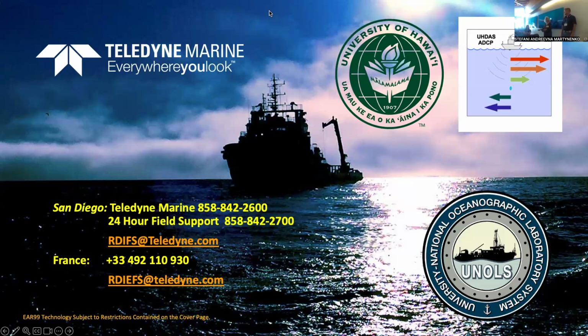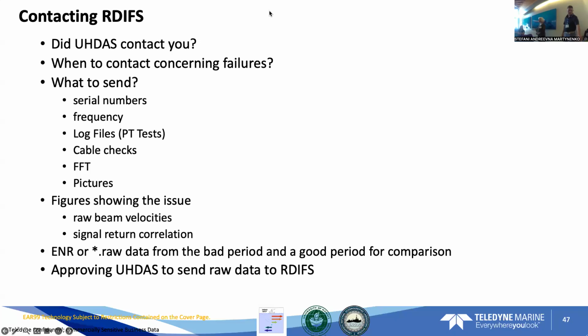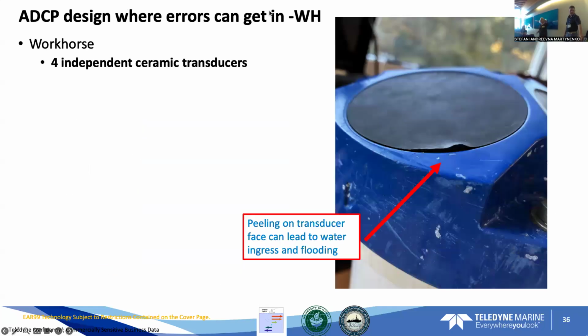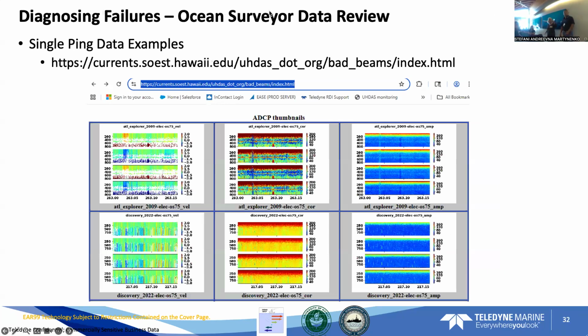In our documentation, there's a section near the end with a large number of figures showing different categories of things where you can recognize it in either the processed data or the raw data. And this one here is an even larger collection of different kinds of errors that you can see in the single ping. On the UHDAS display, somewhere down on the left towards the bottom, it says diagnostics, and there's one that says beam velocities and beam amplitudes, and that's where you can see these exact things.